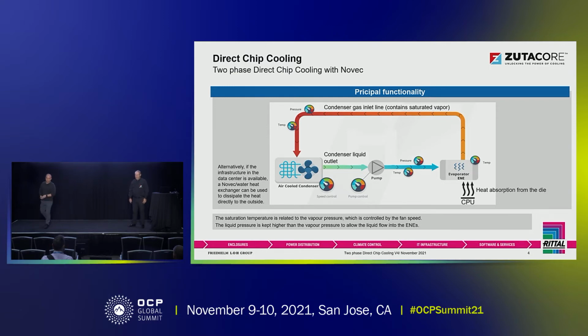Okay, hi. We're talking about two-phase cooling, but two-phase cooling is just the marketing name of it. It's actually dielectric cooling. The important part is that it does the cooling of the direct-on-chip cooling without involving any water in the server and without involving a big change in the data center in the way data centers are being held today. So we need to move from air because, as Thomas showed you, the TDPs are going up, and in 5 to 10 years from now, we won't see data centers cooled by air because the CPUs will be so power demanding.